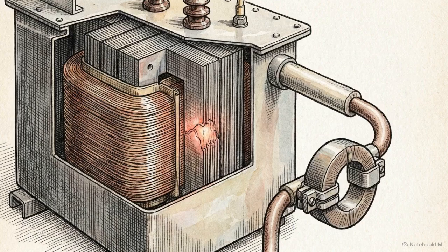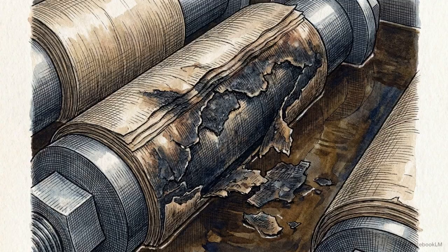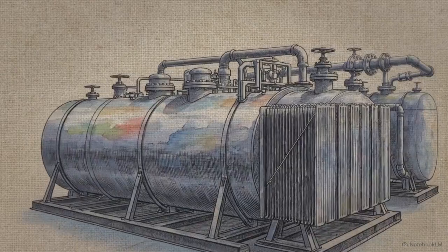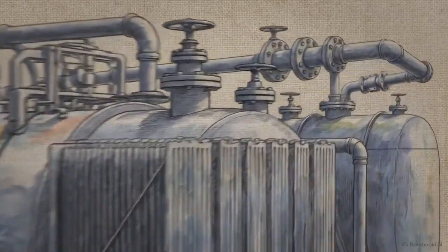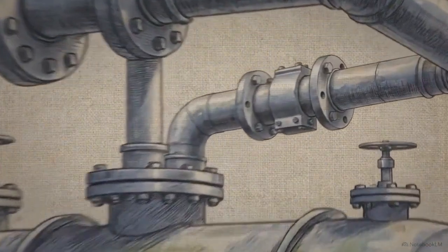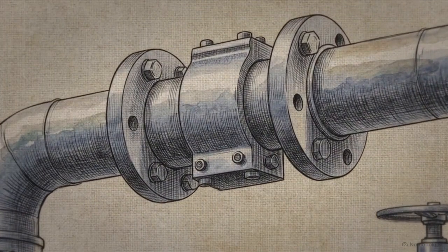Even with perfect mathematics, the electrical matrix has an ultimate limitation. Current transformers only measure current leaving the tank. They are completely blind to low current internal degradation, like the slow breakdown of core bolt insulation. This blind spot requires a shift from electronics to fluid dynamics. Enter the Buchholz relay, a purely mechanical failsafe mounted outside the main transformer body.